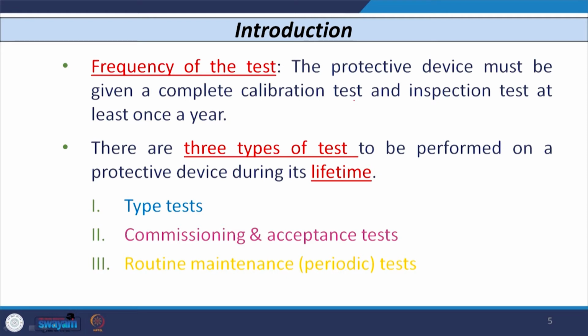So, whenever we consider the different types of tests that are to be performed on the relay or device, usually there are 3 types of tests that need to be performed on the protective device during its whole life. These tests are: one is known as the type test, the other is the commissioning and acceptance test, and the third is known as routine maintenance or periodic test. Let us discuss each of these 3 tests one by one.